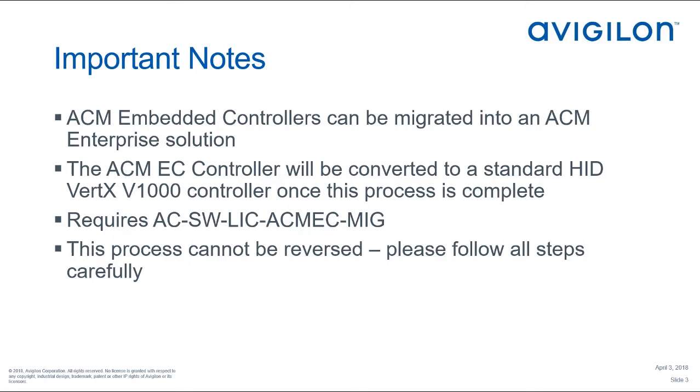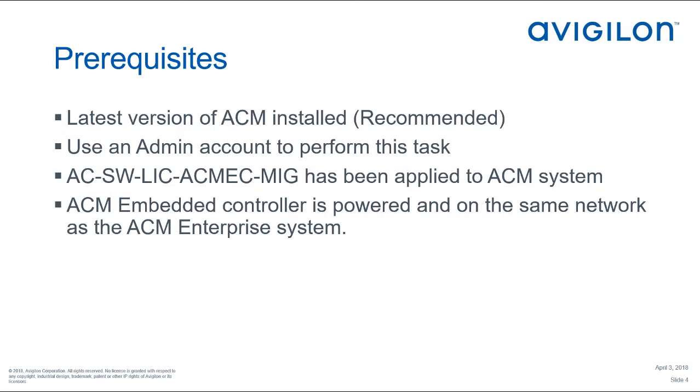The last point is extremely important. Once an ACM EC controller has been flashed, it cannot be reverted to an embedded controller. It is important to ensure you fully understand that there is a risk of causing the controller to be inoperable if this process is not carefully followed.